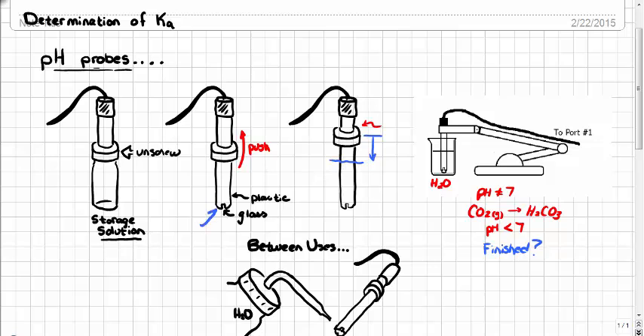And so as you're pushing this, as you're reinserting the pH probe into the storage solution, be very aware of the fragile tip at the end, and remember that the pH probe, when it's actually in the storage solution, should not come into contact with the bottom of the vial, so there should be no contact at this point. Be very careful with this, and please don't simply push the pH probe into the storage solution down to the bottom and then attempt to push the lid into its correct position. The screw lid for the storage solution should always be adjusted before the pH probe is put into the storage solution vial.